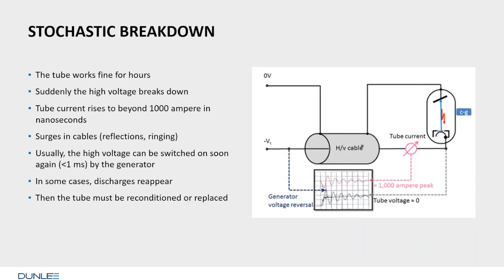The stochastic breakdown is an electric event, and here you see a circuitry of a standard equipment, an X-ray tube attached with a cable to a generator, and suddenly this X-ray tube turns into a switch and short circuits the high voltage. Very suddenly, this creates a voltage surge which moves into the cable back to the generator, and it takes a while until it hits the generator. But on this side here of the generator, the surge reverts sometimes its polarity and moves back into the cable until it again hits the tube. This tube is really a short circuit, with only 100 volts difference left between anode and cathode, because there's really a big plasma cloud then between anode and cathode.